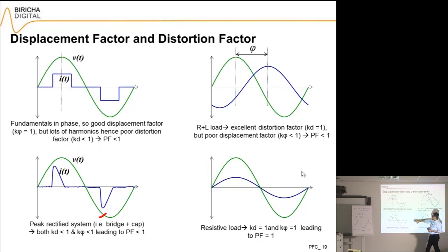Then on this one, this is the one that is closest to what you will see in a power electronic load, power supply, or a peak rectified appliance, whereby you have got a sinusoidal voltage but you've got this peaky current. You will see that the peak of this is not quite in phase with that, so there is a little bit of displacement factor issue.